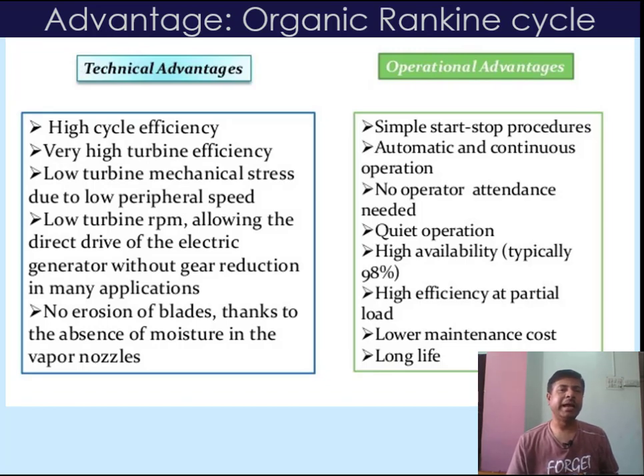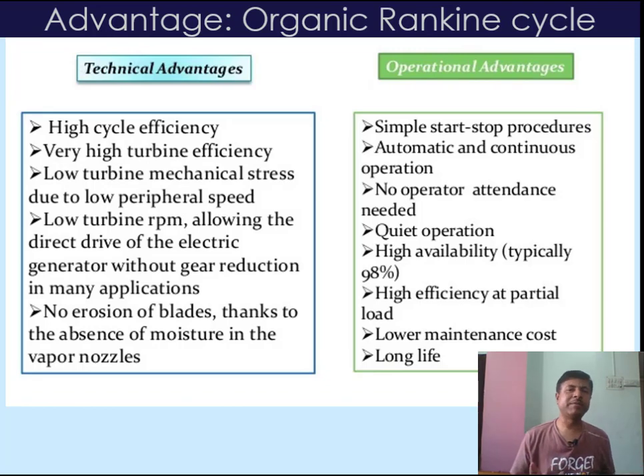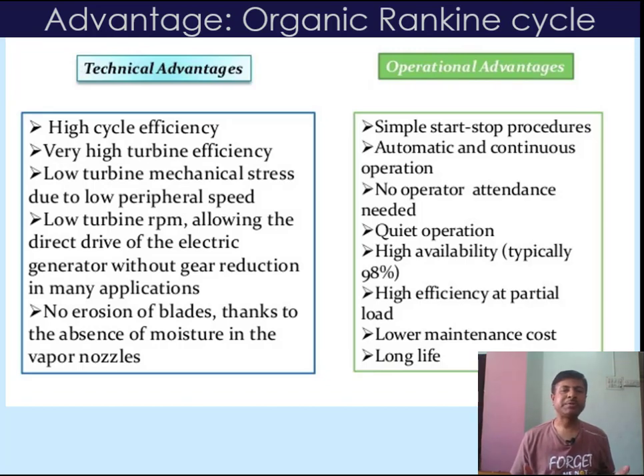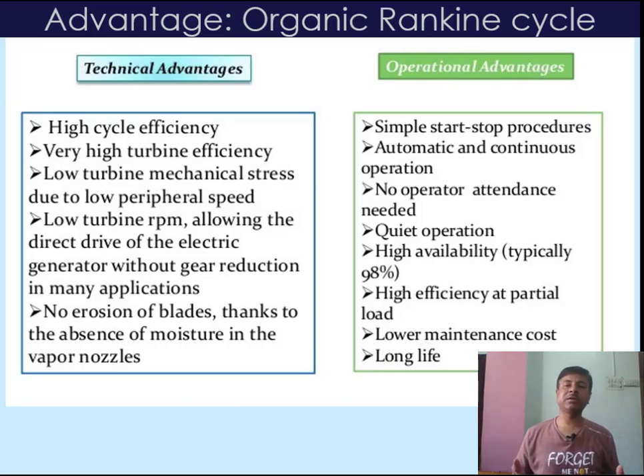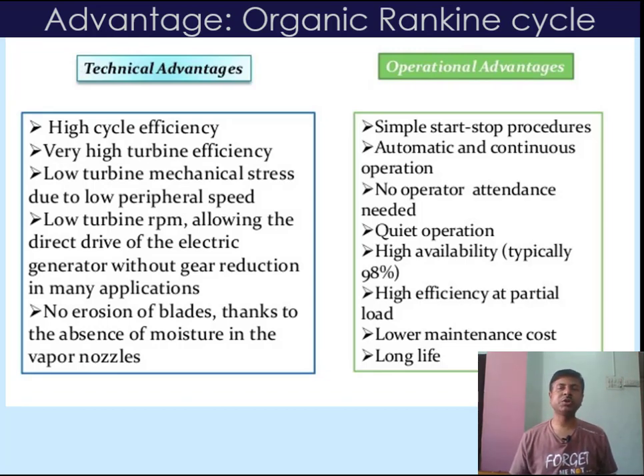The technical advantages include high cycle efficiency, very high turbine efficiency, low turbine mechanical stresses due to low peripheral speed, low turbine RPM allowing direct drive of the electric generator without gear reduction in many applications, and no erosion of blades due to the absence of moisture in the vapour nozzle. The operational advantages are simple start-stop procedures, automatic and continuous operation, no operator attendance required, wide operation range, high availability of around 98%, high efficiency at partial load, low maintenance cost, and longer life.